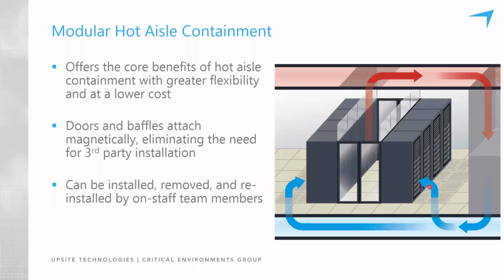And when there's excess conditioned air flowing through the cooling units and through the room, then it doesn't matter whether you have full containment or partial containment, hot or cold aisle, there will be bypass airflow. And I'll make that clear in just a moment.